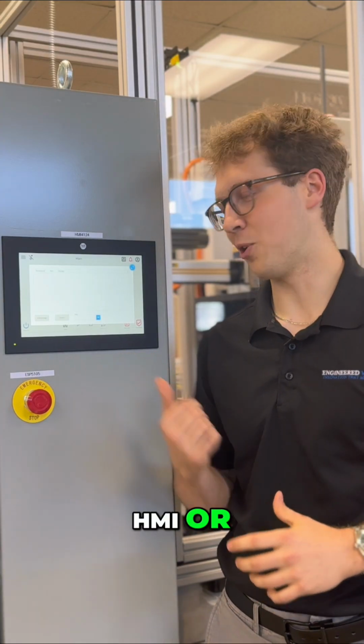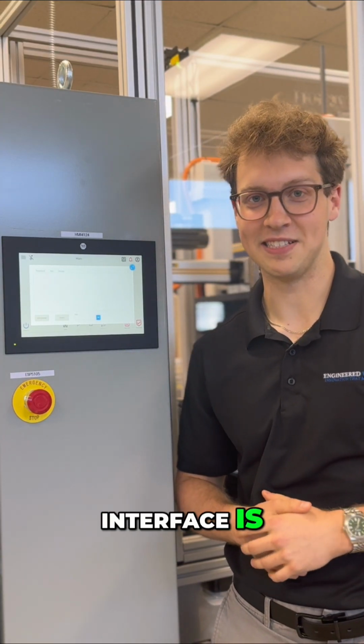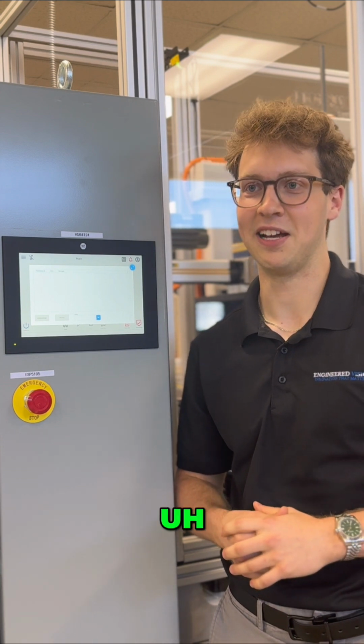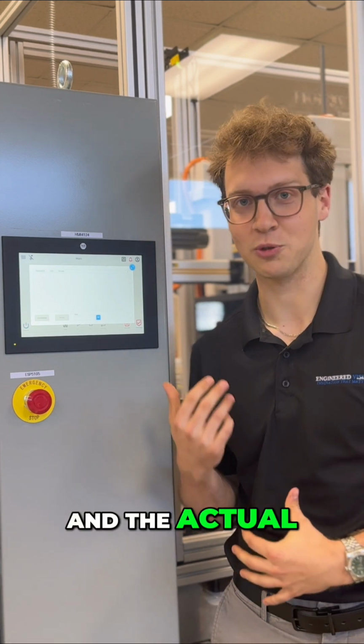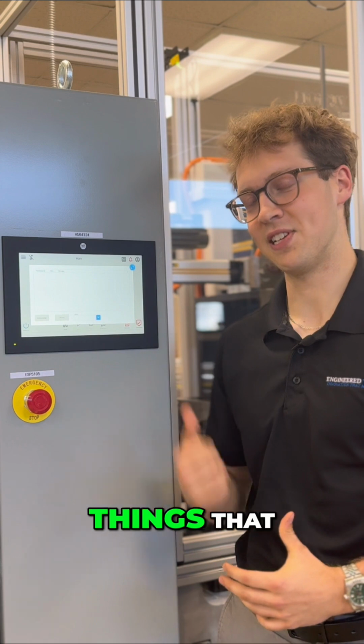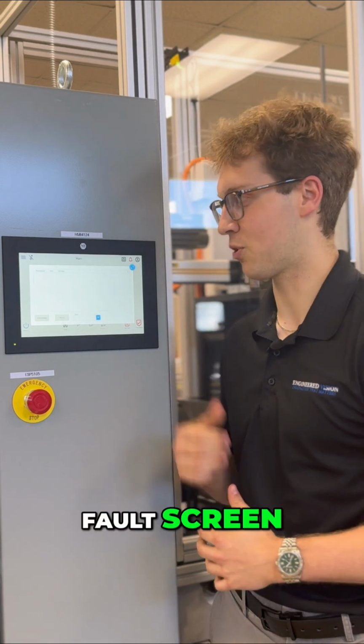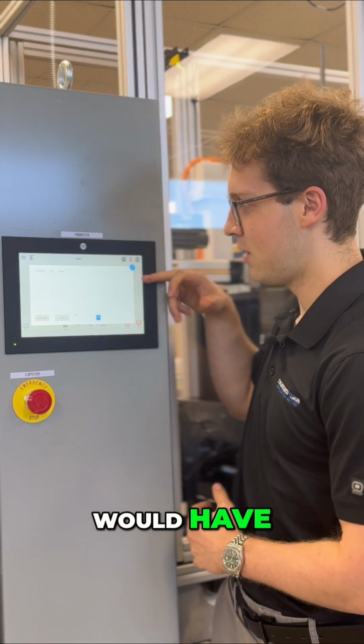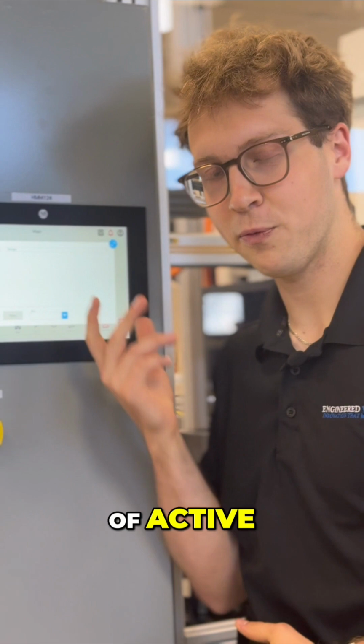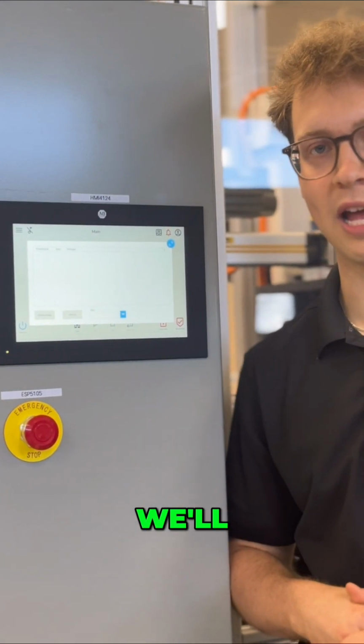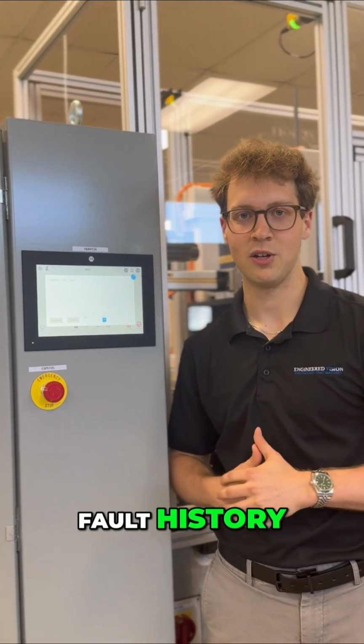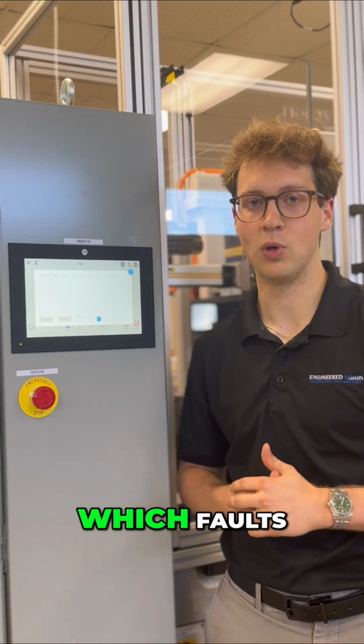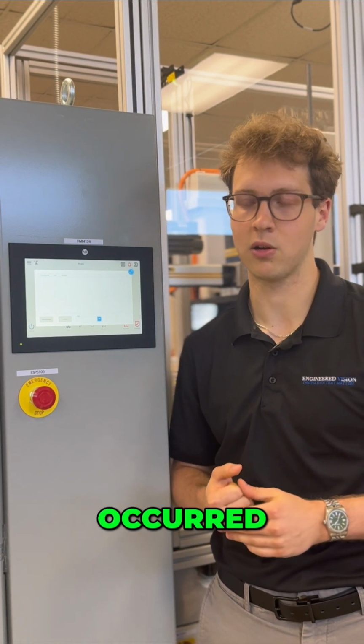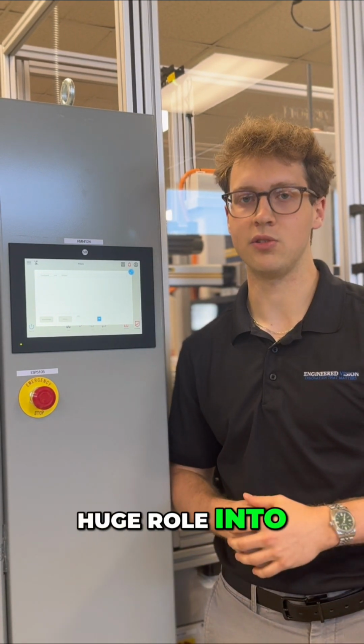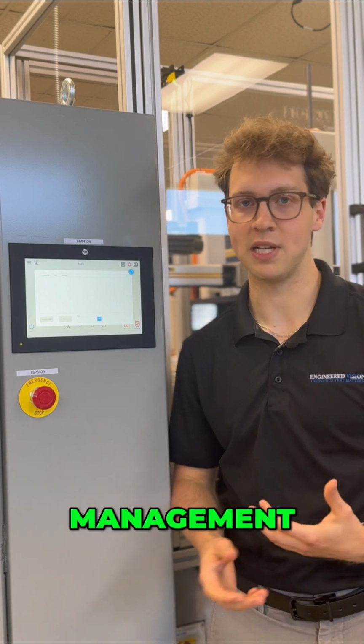The HMI, or human machine interface, is exactly what it sounds like. It's the interface between the operator and the actual machine. One of the biggest things that they'll interact with is the fault screen. So here we would have sort of a list of active faults, as well as a lot of the times we'll have a fault history, where the operator can see which faults have occurred in the past and when they occurred. This again plays a huge role in the alarm or fault management system.